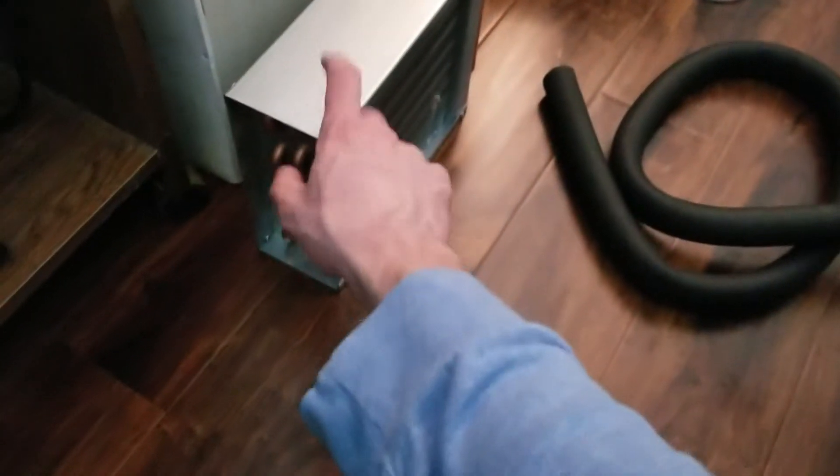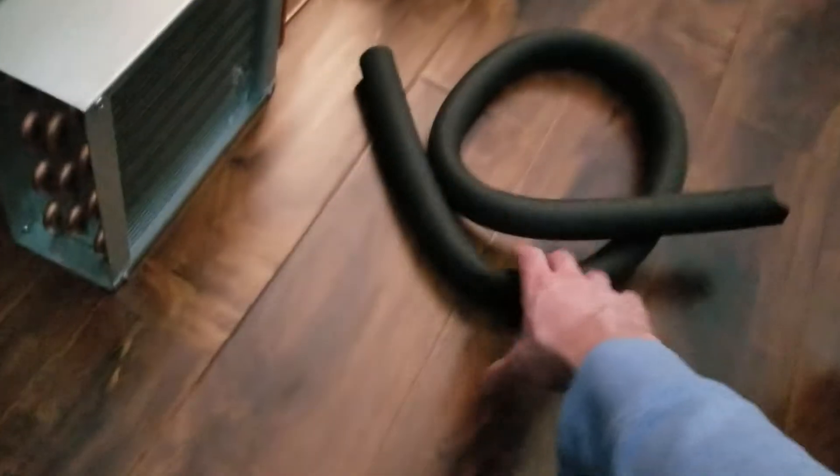Here's our condenser water in and here's our condenser water out. So the next step is doing the piping for the condenser water and ordering the circulator pump, then getting it tied into this coil. Here's some more ArmaFlex that I'll apply once we do a pressure test and a vacuum test. Once everything holds, I can put a charge into the unit — and getting it running is really the very last thing I'll do.